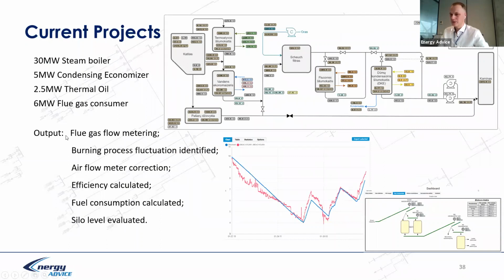For example, for output, what we delivered is the flue gas flow metering. I described it earlier: the installed flue gas flow meter showed 29 ton per hour, and we calculated 15 ton per hour, and everything is balanced, so it's just bad data. Burning process fluctuation was identified, and an airflow meter correction was made, but the installed airflow meter also has a 10% error. Efficiency is calculated, fuel consumption is calculated, and silo level evaluated. We put fuel into the silo and evaluate the reading from the SCADA, the control system that monitors the silo level. According to calculation, we know the delivered fuel, and we know the burned fuel from the digital twin equations solution. So we monitor fuel, and it's trending quite well.